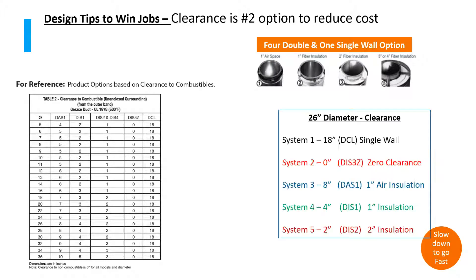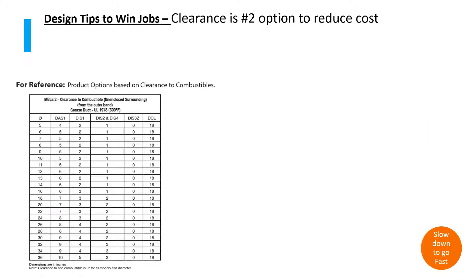Let's do another one. Our next diameter is 26 inches. The first system has 18 inches of clearance, so once again the DCL product. Zero clearance is the DIS 3Z, then the DAS 1, which is air insulation between the double wall product, 1 inch of insulation, and 2 inches of insulation.